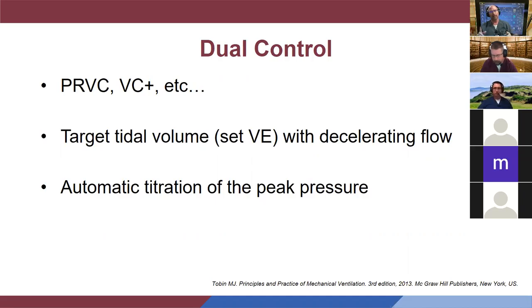But I do caution you, if you do attempt to use this mode, and maybe a lot of you have experienced this before, remember the algorithm. Okay, because if you set a tidal volume of 500, and let's say I've got someone like Darren on the ventilator, and he wakes up and he's just taking these enormous breaths. His inspiratory demand is just taking these big, giant tidal volumes. And now I'm looking at the vent, and it's exhaling 750, 800, 850. What does the algorithm say to do? Well, if the tidal volume is more than the set volume, it's going to start titrating pressure down to get back to the set tidal volume. Well, what does that do to Darren?